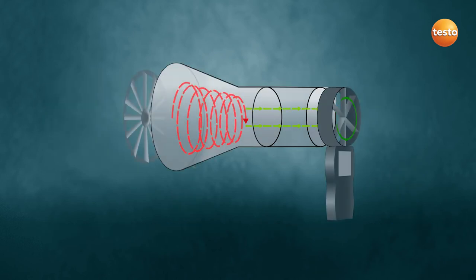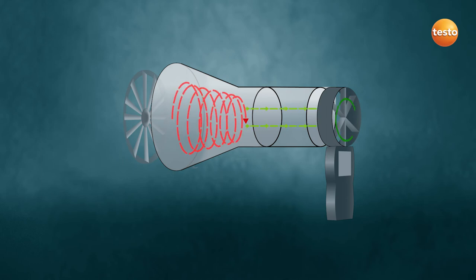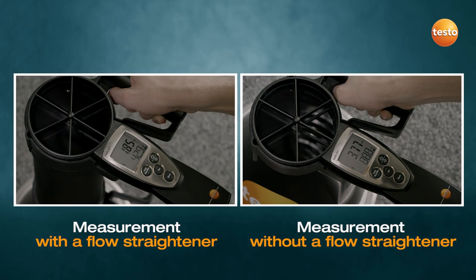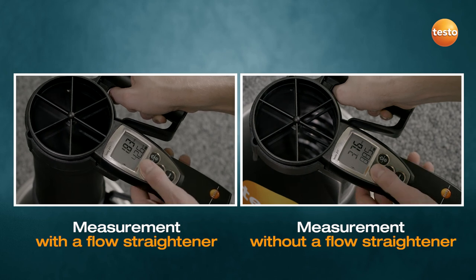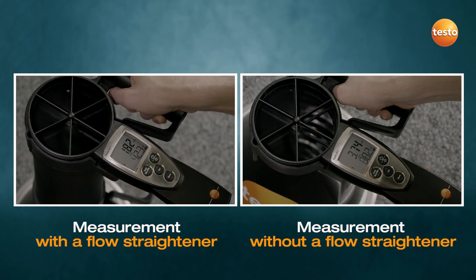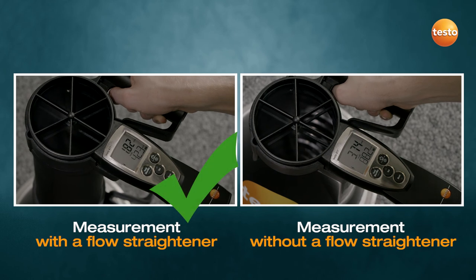What does the flow straightener do? With the patented testo 417 flow straightener, any rotational movement of the air is first calmed and changed to a straight flow direction. This directed airflow is then reliably recorded with the vane. That way, the most accurate measurement results are achieved quickly and easily.